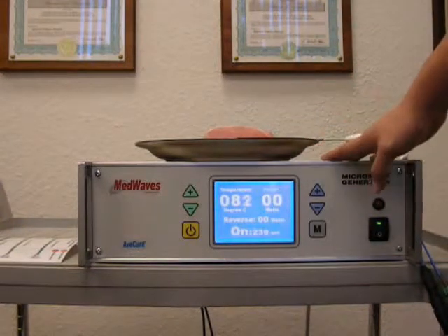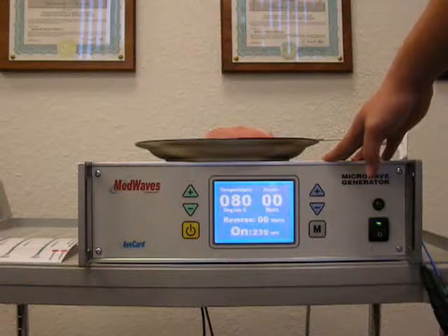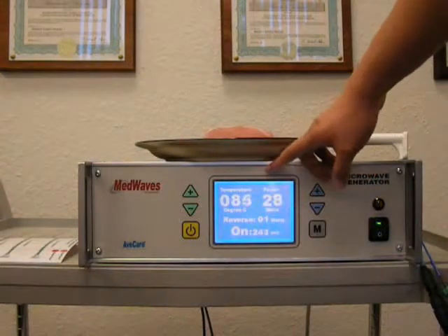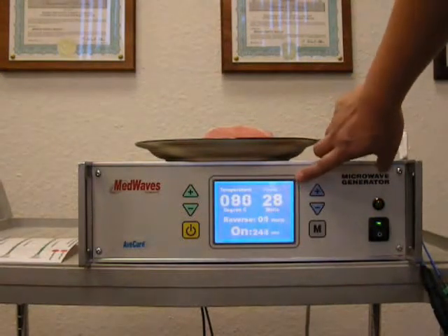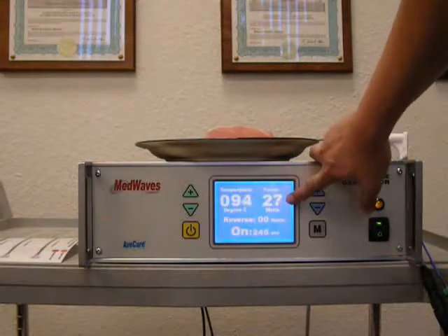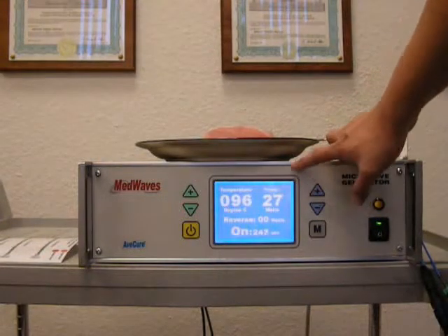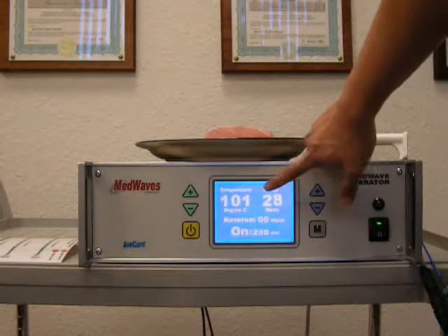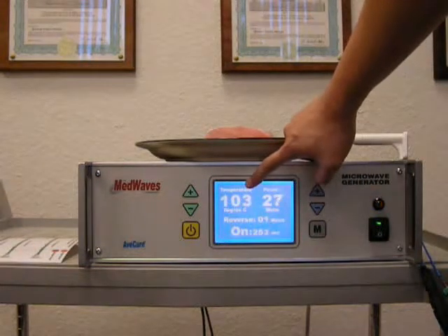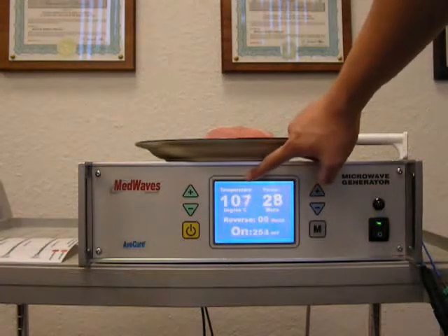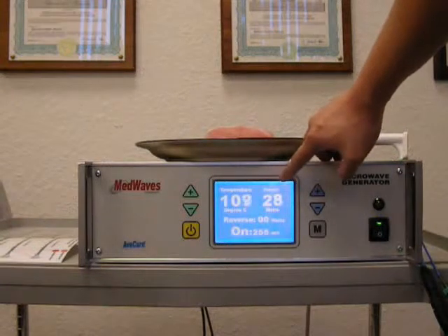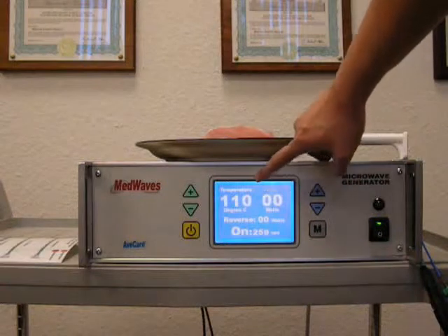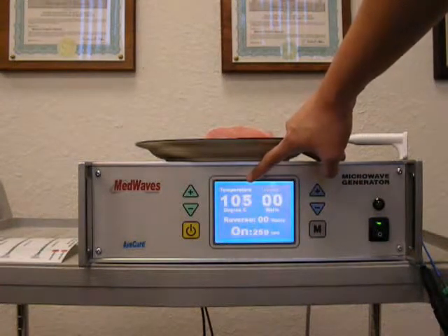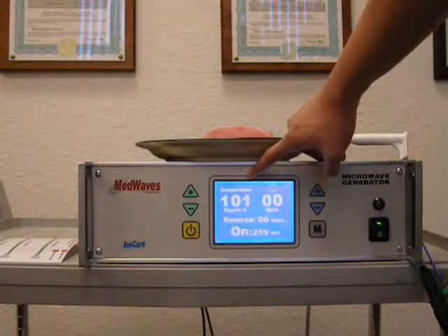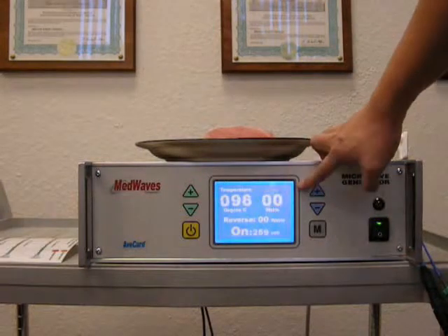So for this ablation, the temperature was set at 110 degrees. Because it switched over to power mode, the default power is 28 watts. The generator will use 28 watts to bring the temperature up to 110 degrees. Once the temperature is reached, the forward power will stop. And then the temperature will drop down to 80 degrees. Once it reaches 80 degrees, the power will turn on again.